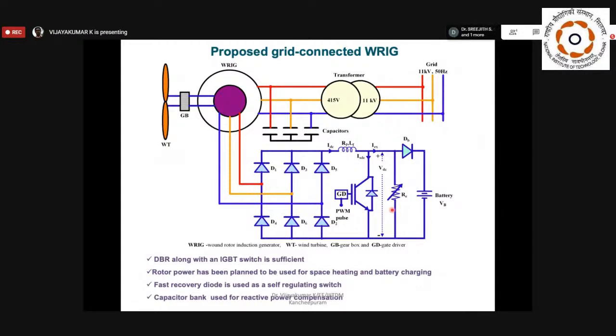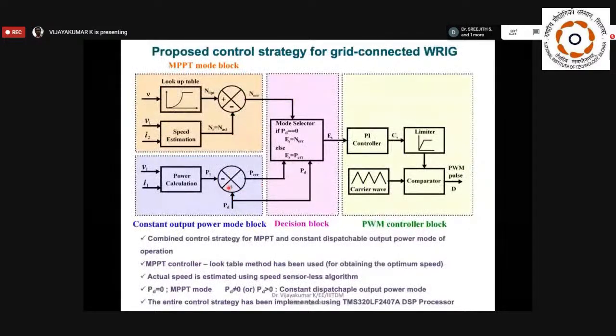Even in the control strategy, we have proposed both MPPT as well as constant output power mode. For MPPT operation, we have implemented a speed sensorless algorithm. Here we have estimated the speed with the help of stator voltage and rotor current. From the stator voltage you get the frequency, and from the rotor voltage you are able to get the slip frequency. Once you know the slip frequency and the stator supply frequency, it will be easy to estimate the speed by using the relation between the slip and synchronous speed, right? So that's what we have done here.